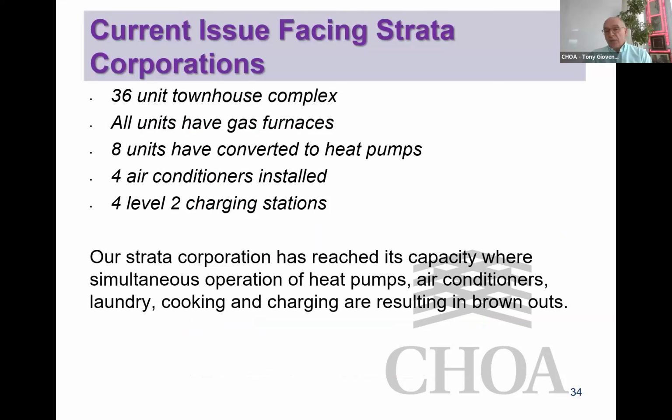We've talked about the scenario, but this is a problem that we're coming up against quite a bit right now. And this is fairly common. Townhouse complex, all the units with gas furnaces, 8 have converted to heat pumps, 4 have air conditioners. There are 4 level 2 charging stations, but the Strata has now reached its capacity.